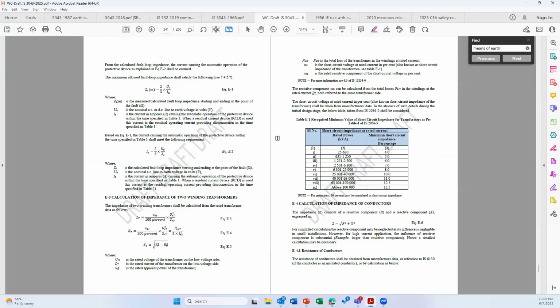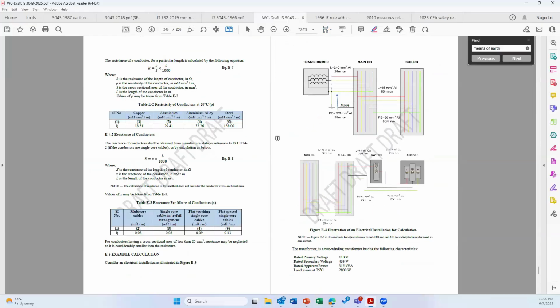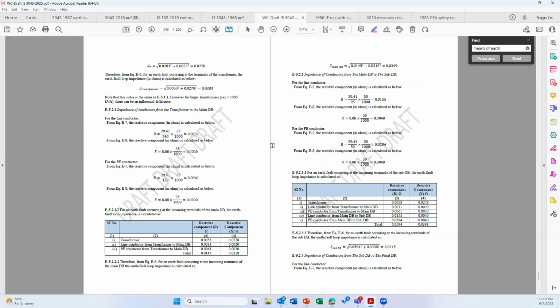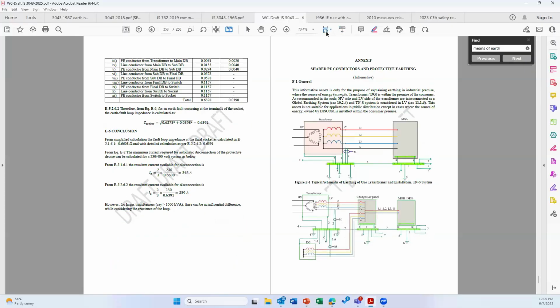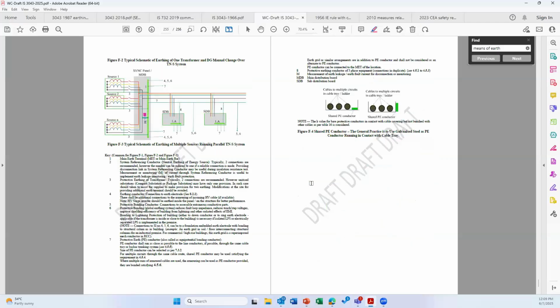Then a detailed calculation as an example is being included, because when you calculate the fault loop impedance, you have to consider the resistance and reactance of large conductors. For the bigger size conductors, you should consider the resistance and reactance. A detailed example is being given. Then the last information is a shared PE conductor. For example, if you have multiple runs of cable going to one part of the electrical installation, you don't need to run multiple protective earth conductors. You can run one protective earth conductor. That information is being given in this particular annex.